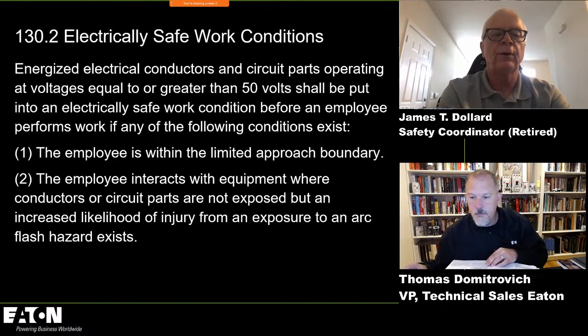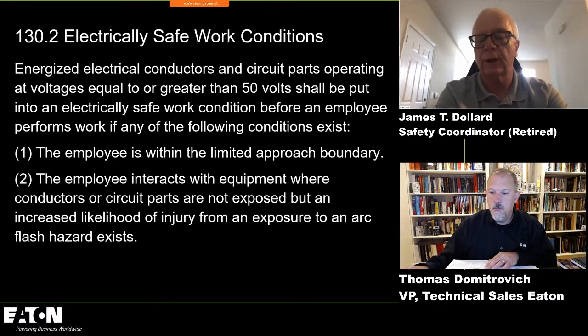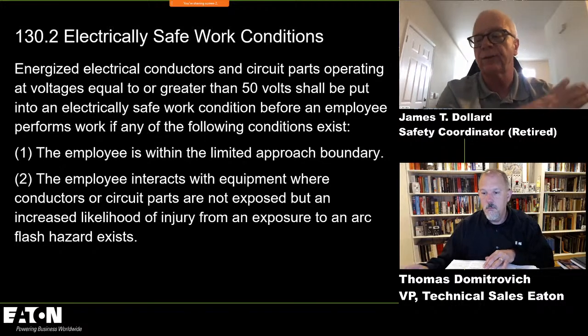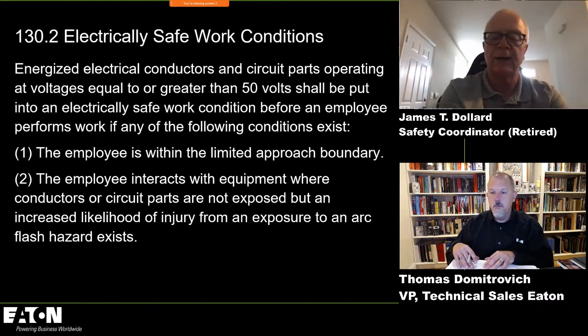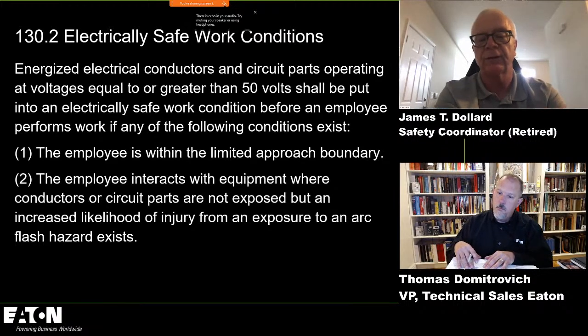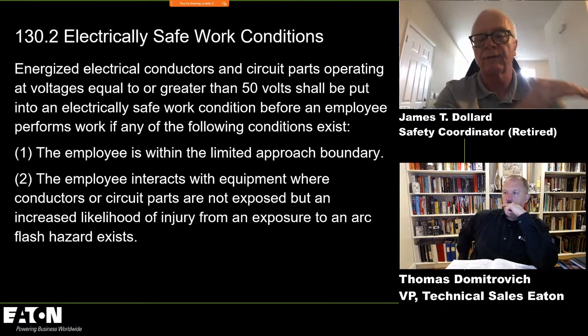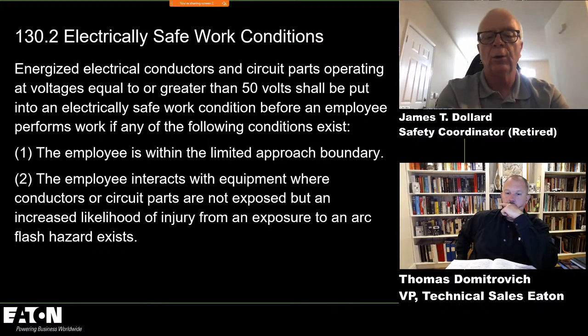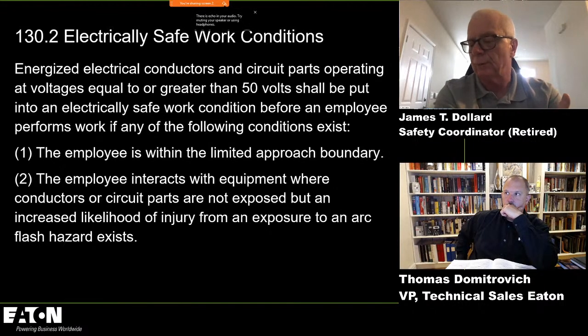And then in 130.2(A), you get into energized work. There you get into what I call your justification thresholds: infeasibility, additional hazards or increased risk, less than 50 volts, and normal operation. But taking a look at this text, it's going to tell you that all electrical conductors and circuit parts at 50 volts or greater have to be put in an electrically safe work condition before you get within the limited approach boundary. And the limited approach boundary from 50 volts to 750 volts AC is 3 feet 6 inches.